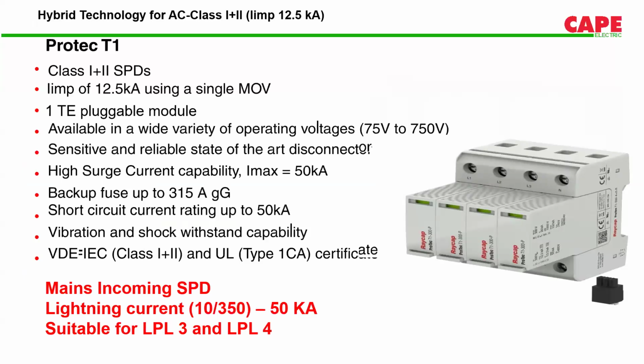These also have an impulse current of 12.5 kA, which is the minimum requirement as per the National Building Code of India 2016. Again, I am repeating this point because there are a lot of SPDs in the Indian market which have an impulse current of 5, 6, 7, 2, 3 kiloamperes, and they call themselves class 1+2 SPDs. As per Indian standards, strictly they are not 1+2 SPDs. They are strictly type 2 SPDs. Anything less than 12.5 kA means a type 2 SPD.